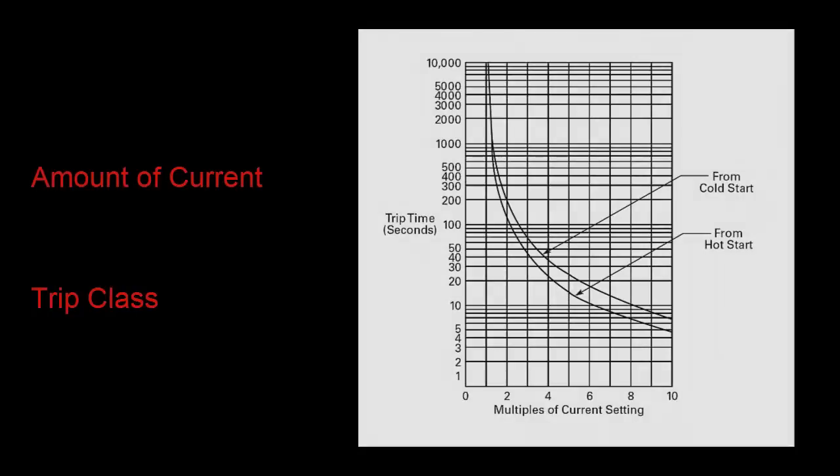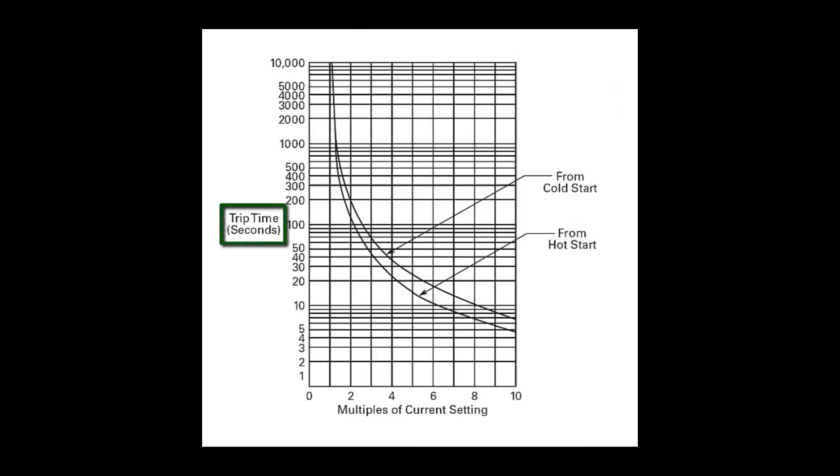And we answer this question using what we call time-current trip curves. This graph with a logarithmic scale shows time in seconds on the y-axis and current as a multiple of the FLA dial setting on the x-axis.